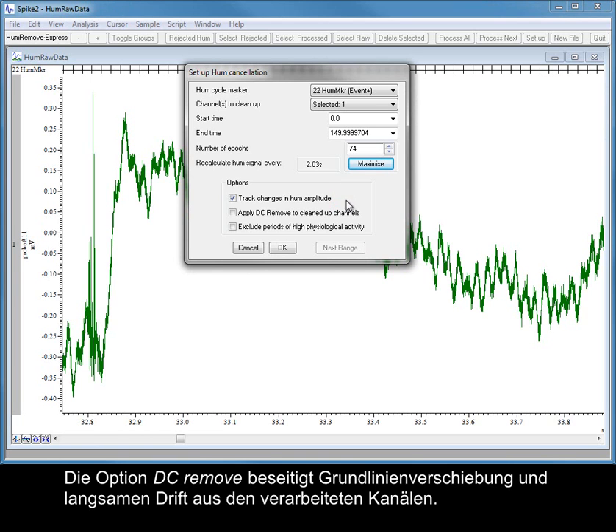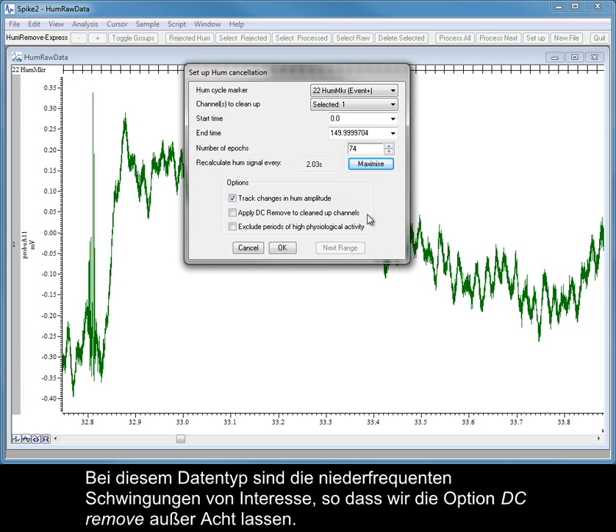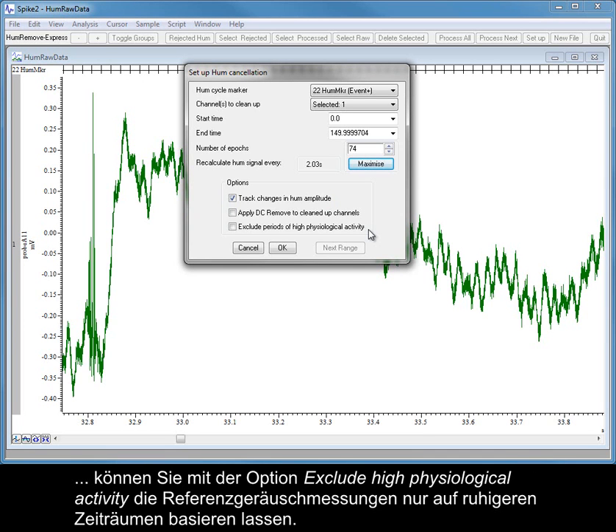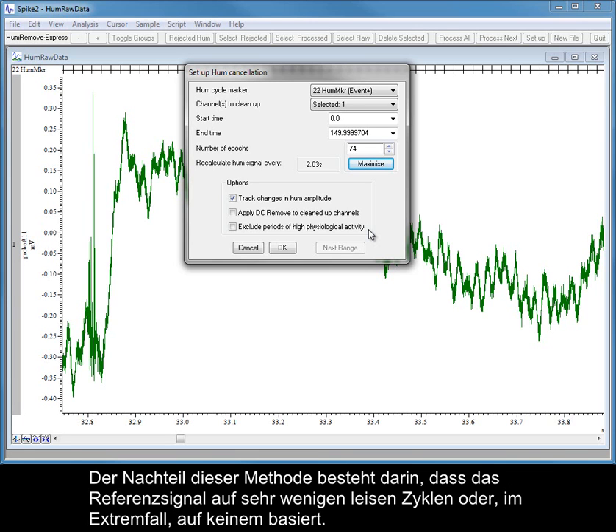The DC Remove option removes baseline offset and slow drift from the processed channels. In this type of data, the low frequency oscillations are of interest, so we will leave the DC Remove option unchecked. If your recording contains bursts of activity alongside quieter periods, you can use the Exclude High Physiological Activity option to base the reference noise measurements on the quiet periods only. The drawback with this method is that the reference signal could be based on very few quiet cycles, or in extreme cases, none at all.